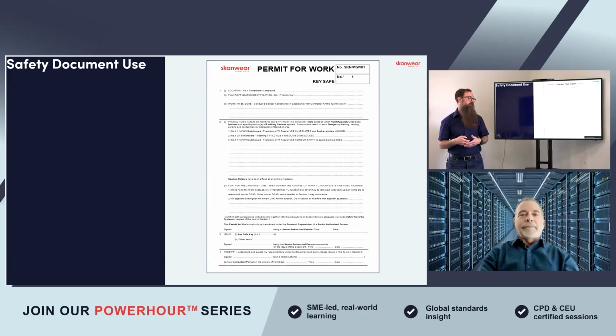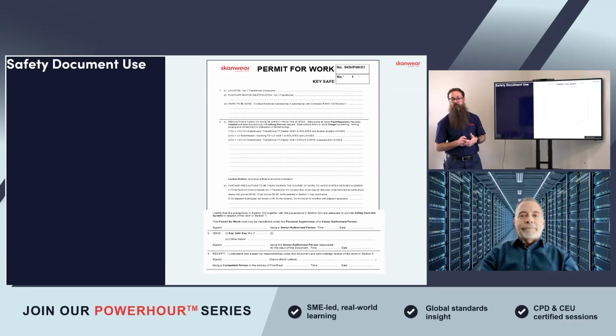Once proven dead, the works in section 1 of the safety document can continue. All the adjacent switchgear will remain live for the duration - don't touch or interfere with anything adjacent. It's clear that this is the only piece of equipment to be worked on.